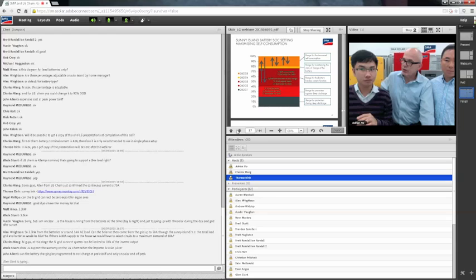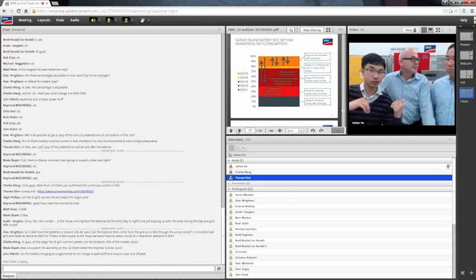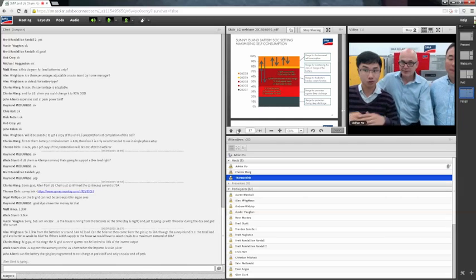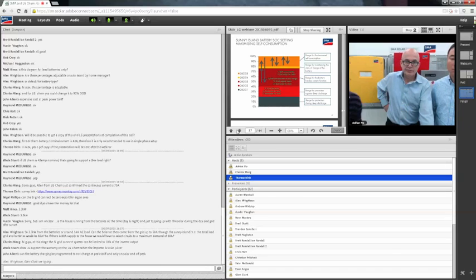I think we do a 10% DOD, down to 10%, so you can use 90% for the LG Chem products. You can use up to 90, but if you've allocated 90 for self-consumption, you have nothing for backup. When the grid goes away, that's it - that's it remaining.